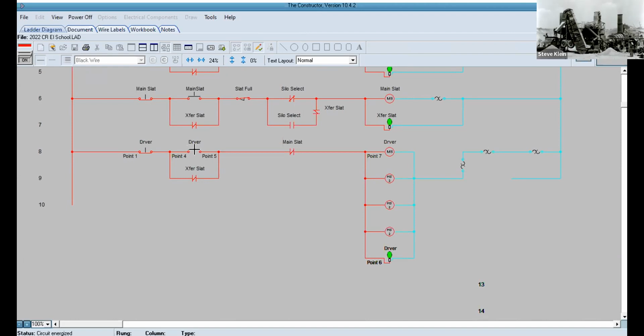That's a common setup you'll see on any drum running 4 electrical motors or such. If they've got separate motors, they'll all pull in alike. And if they run one big main starter, you'll still see a set of overload coils for each dryer. In other words, they might have one great big size 7 contactor to start and power all 4 motors, but the overloads will still be 4 separate overload blocks with 3 overloads each going out to each motor.